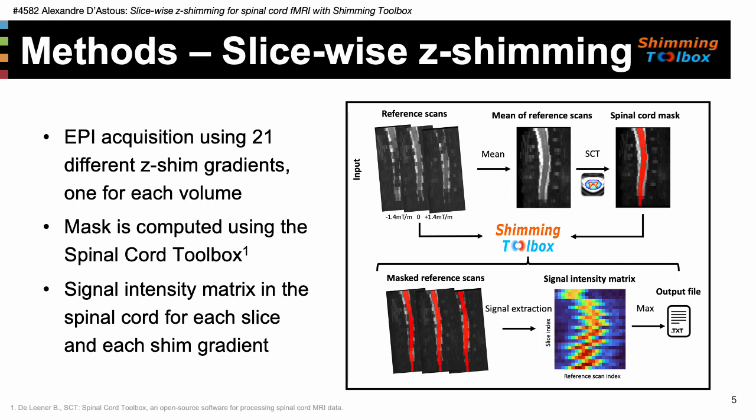The processing of those coefficients was implemented in shimming toolbox and used to generate a text file to perform dynamic z-shimming. Overall, the processing took 15 seconds, including DICOM-to-NIfTI conversion, spinal cord extraction, and shimming calculations, which itself was around one second. This allows no time to be wasted while shimming at the scanner.